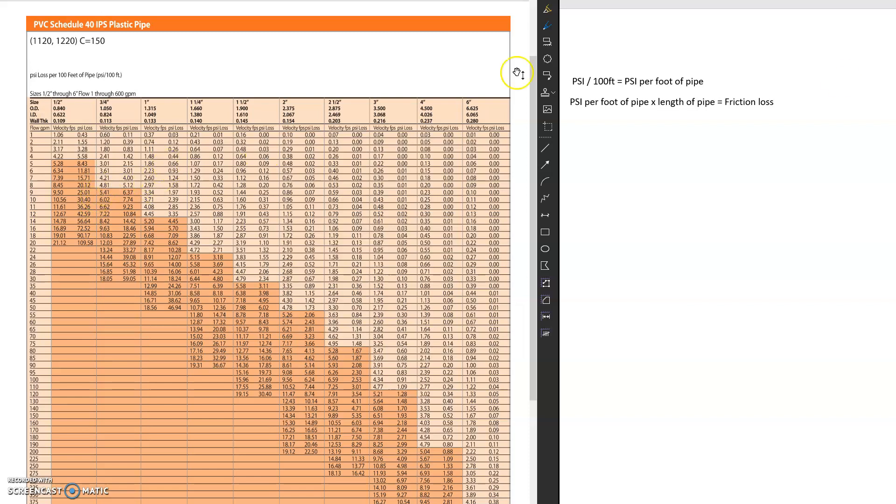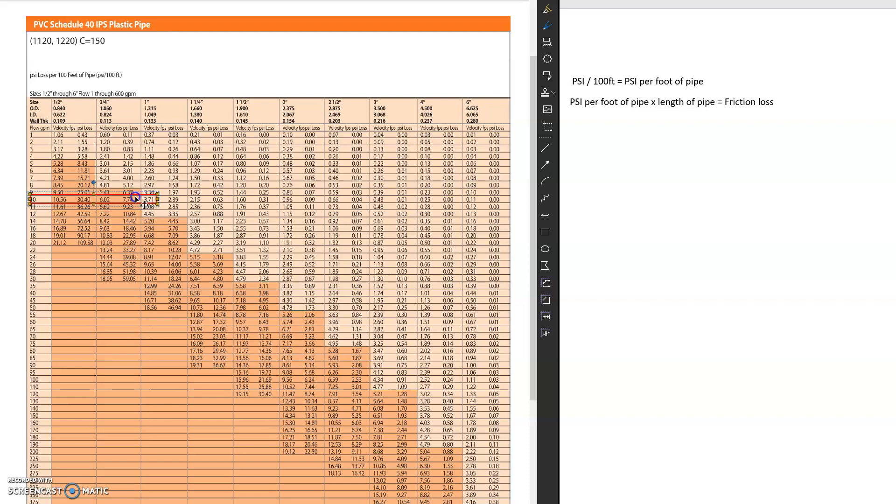And so when we go over here, let's say I have 10 GPM and then we know for 10 GPM that the velocity, we would have a 1 inch pipe because that's 3.71 feet per second. But now if we want to know the friction loss, how much pressure we're losing through the pipe, because that's very important, you guys will be learning this in the next couple weeks.